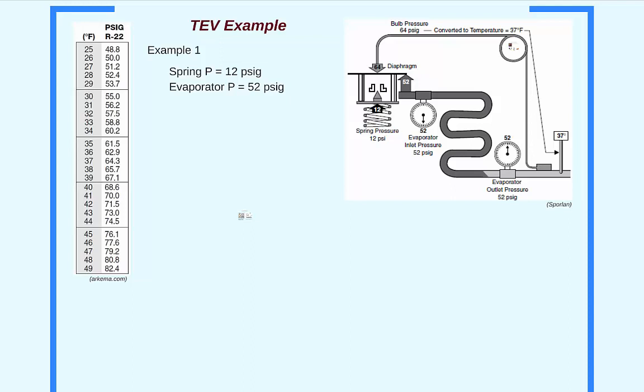sensing bulb. At 52 psi, the evaporator's saturation temperature is approximately 28 degrees Fahrenheit. The temperature measured at the sensing bulb is 37 degrees Fahrenheit. Since the thermostatic charge is also R22, the same table is used to determine the bulb pressure. When the sensing bulb is exposed to 37 degrees, the pressure exerted on the diaphragm is approximately 64 psi gauge.